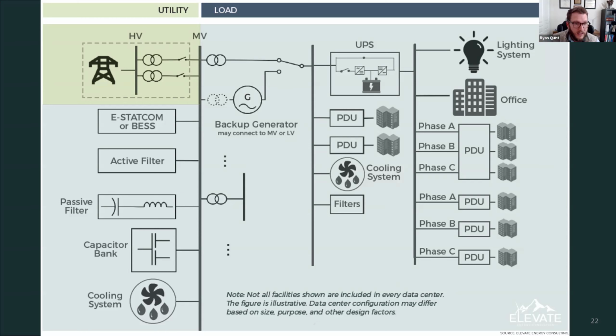So the need for EMT analysis, the need to understand what's inside the facility and how the devices inside the facility behave, matters a lot. You've got PDUs, cooling systems, lighting loads, backup generation, potentially grid parallel generation, filters, and then maybe even more advanced capabilities like battery energy storage behind the meter, or even e-STATCOMs helping smooth out some of the variability of AI loads.